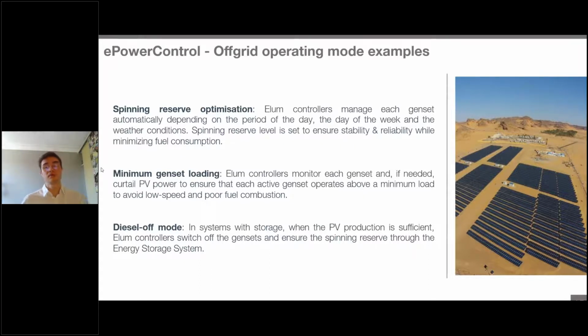For example, if you have 4 different genset units running at a moment when only one genset could be used because you have an important PV production available, we'll make sure that you have only one genset turned on, ensuring you are running this genset at a more efficient loading. So we have all these control strategies that are a bit more complex and about optimization for off-grid applications.